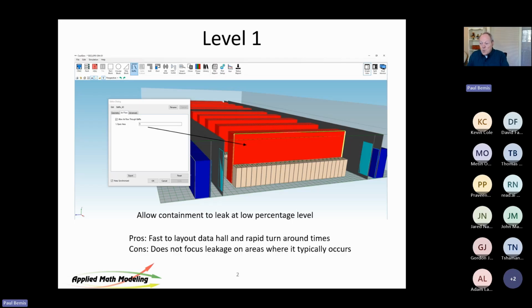Now, level one is I'm going to let this surface here leak. This is the containment surface where hot air is contained here. Here are the servers. You can see these little arrows indicate airflow. So it's blowing into the contained area. There are grills at the top of this that are probably hidden. I don't see them. But you can let this surface leak. Generally, we let it leak at about 5% using a baffle object. That's a perforated plate. You can think of it as that.